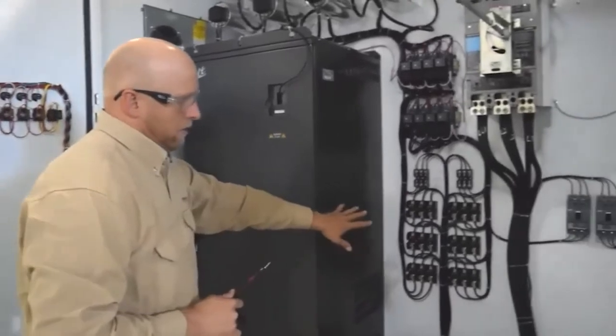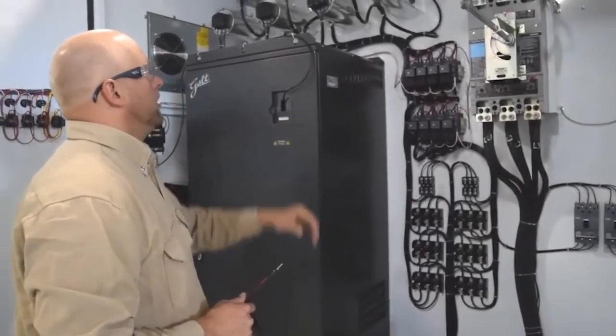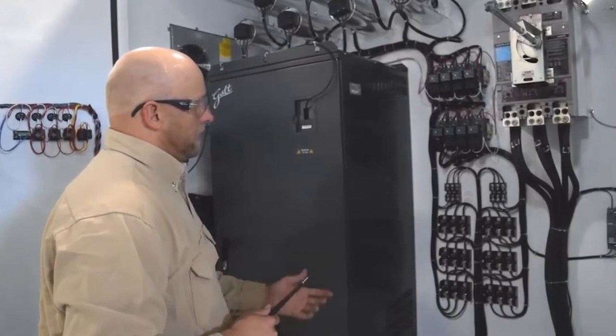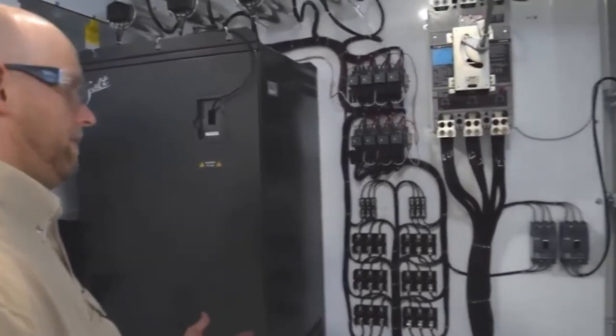All right, so now that we checked the capacitors out, everything looks good. I would go through at this point, measure all the fusing on it, check it out. So I'm going to measure a few of the fuses inside the cabinet.